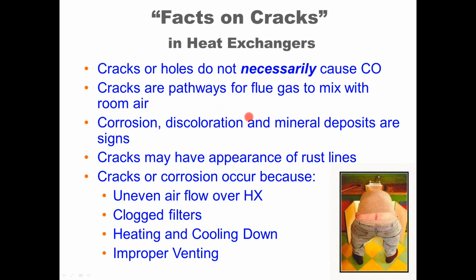Corrosion or discoloration and mineral deposits can be signs of cracks. They may look like rust lines. Some of the underlying reasons why cracks or corrosion may occur are uneven airflow or insufficient airflow over the heat exchanger. Clogged filters can cause not enough airflow to be present. Other causes are excessive cycling, heating and cooling, maybe because of high fuel pressures, improper or excessive airflow over the heat exchanger, and improper venting that may cause temperatures to back up inside the heat exchanger. So again, setting up and maintaining per manufacturer's specifications can save you from these issues with heat exchanger problems.